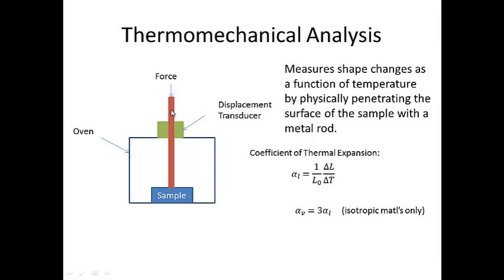A displacement transducer measures the displacement of the rod as a function of temperature. This allows us to calculate the coefficient of thermal expansion as the change in the dimension of the sample divided by the change in temperature times one over the original length of the material. This gives us what's known as the linear coefficient of thermal expansion or alpha sub L.